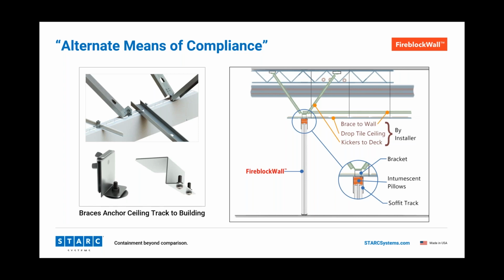An equipment storage closet, as you mentioned, will require a 1 hour fire barrier, whereas a change of use space to something less hazardous may allow a partition to be used. So it's really up to your AHJ to determine what can be done. But again, our system is flexible and can be used in this way. Next.